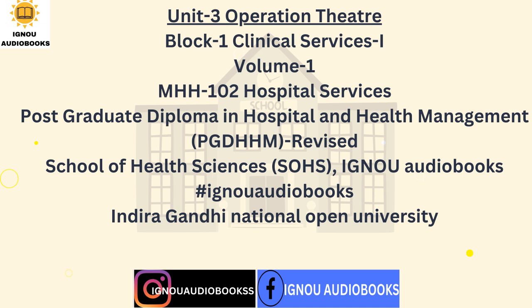together. As a result, audio, video, pendant lights, and room lights all function together, enabling a higher quality and more comfortable surgery for both patients and surgeons. In addition, this advanced integration is more time efficient as it negates the need for switching between multiple equipment. When integrated, all technology can be manipulated from a central command console by a single operator. Integration in OT holds the key for effective application of minimally invasive surgery, robotic surgery and functioning of hybrid OT.